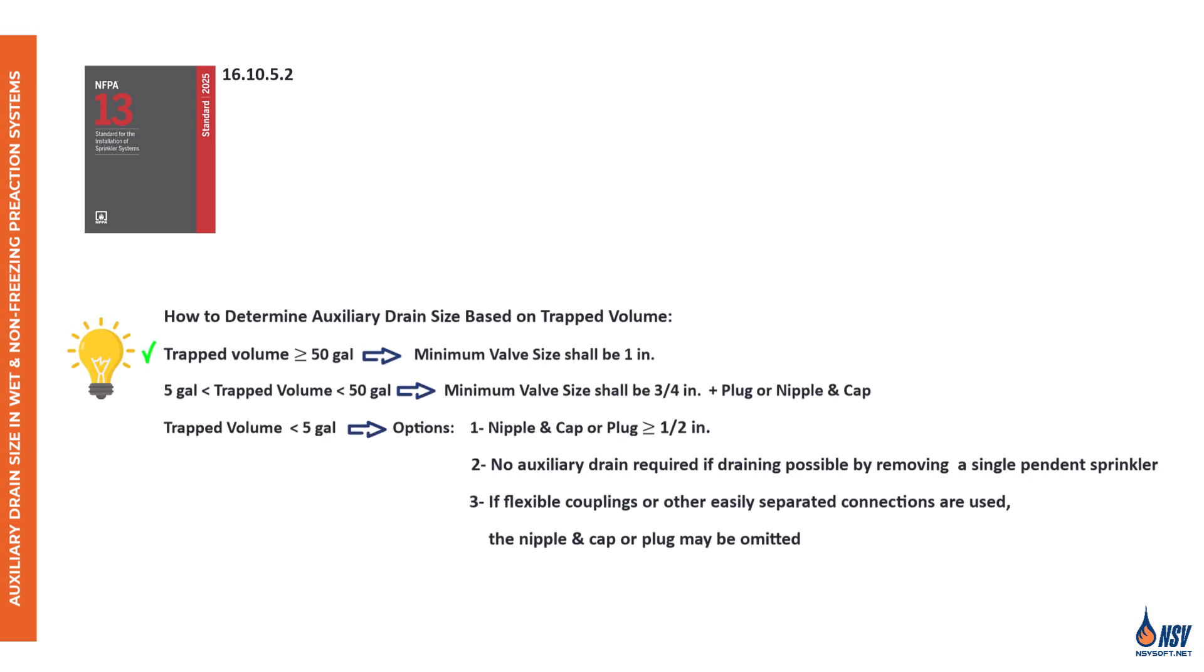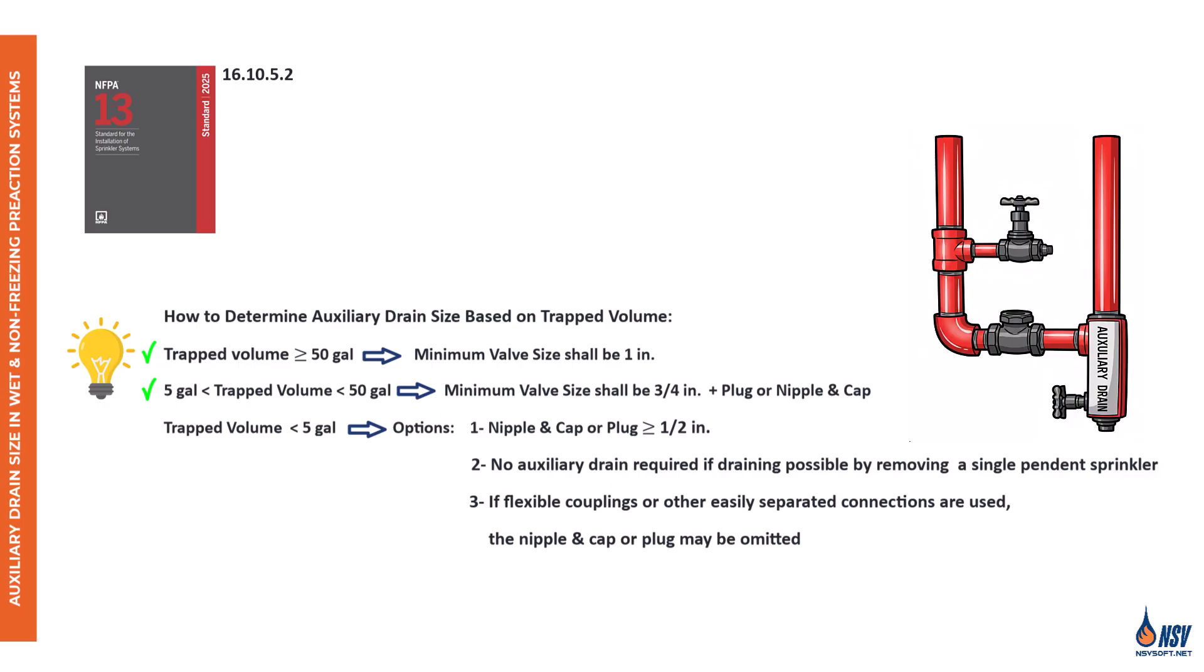So, if the trapped volume is 50 gallons or more, the drain must include a valve at least 1 inch in diameter, piped to an accessible location. If the trapped volume is between 5 and 50 gallons, the drain must have a three-quarter inch valve, plus a plug or a nipple and cap. For trapped volumes less than 5 gallons, there are three acceptable options. Option 1: use a half inch nipple and cap or plug. Option 2: if the section can be drained by removing a single pendant sprinkler, no auxiliary drain is required. Option 3: if flexible couplings or easily separated connections are used, the nipple and cap or plug may be omitted.